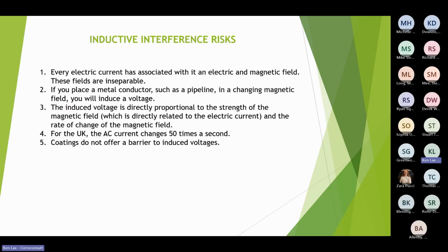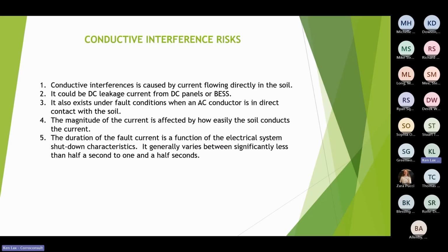So we discussed that you'll always get this voltage induced. Indeed, it's how generators work. That's why they whiz round and round, so that they can have either a rotating magnetic field or a rotating conductor. Either way, it doesn't care. And the other important thing to notice is that the voltage is induced on the pipeline regardless of its coating. It's exactly like a radio wave. It's no different from the radio waves that come from radio transmitters, broadcast transmitters. And if ever you played with radios and aerials when you were younger, you would have realized that a coated aerial still receives signals in exactly the same way as a bare wire does. So there's no protection at all from AC induced voltages provided by coatings.